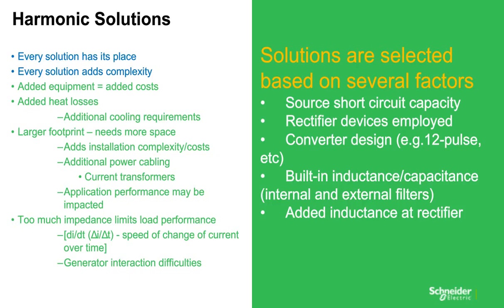And every solution typically has its complexities, whether it be added equipment costs, added heat losses, additional cooling requirements, larger footprint, which means the need for more space, added installation complexity costs, or additional power cabling with the current transformers, and application performance, as well as too much impedance limits load performance. So generator interaction difficulties, speed of change of current over time. And we'll get into a breakdown of what the current solutions are out in the marketplace and how they affect each of the following categories discussed.